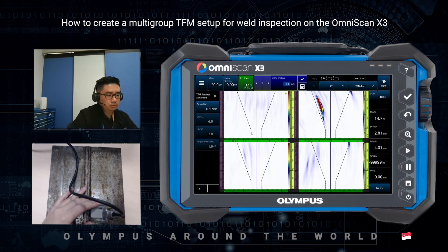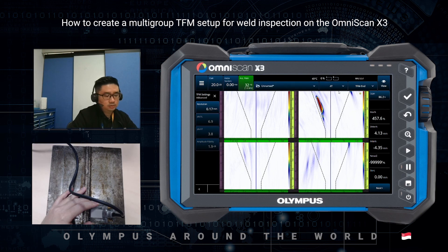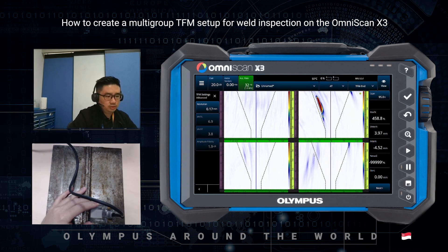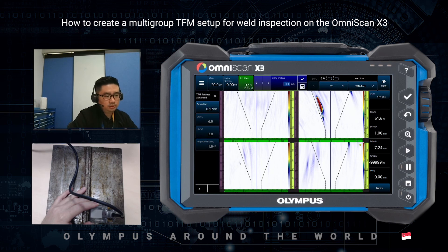We get another signal over here. This one is on the full skip, or 4T, and you can see it gives very high amplitude on the sidewall — so it looks like a sidewall fusion defect. We also see a little bit of it on the 5T and even a little bit on the 3T.